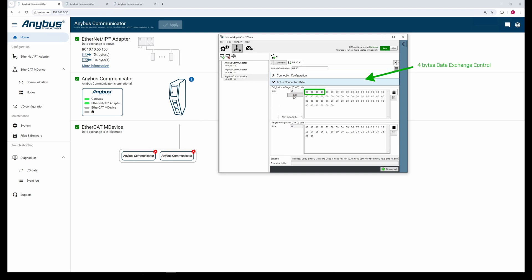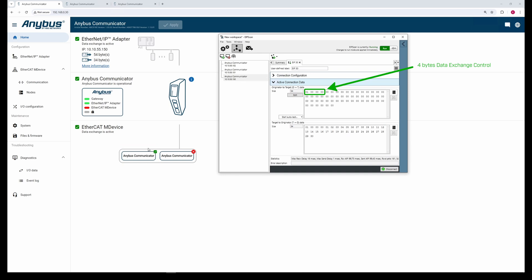The Data Exchange control is binary. To start Data Exchange with the first sub-device, we send a binary one in the first byte of the Data Exchange control. The main device changes status from idle to active and the first sub-device becomes green, indicating that we are exchanging data with it. You can see that the Live List reflects this with a binary one.